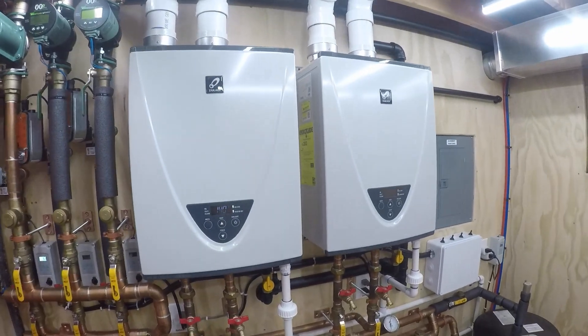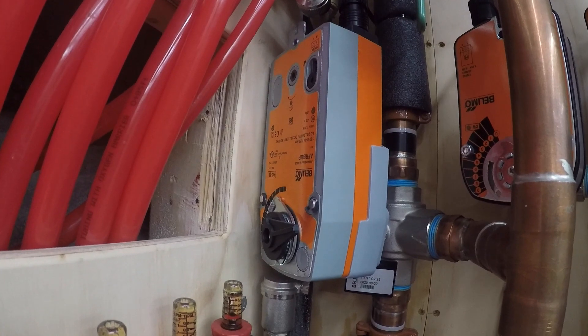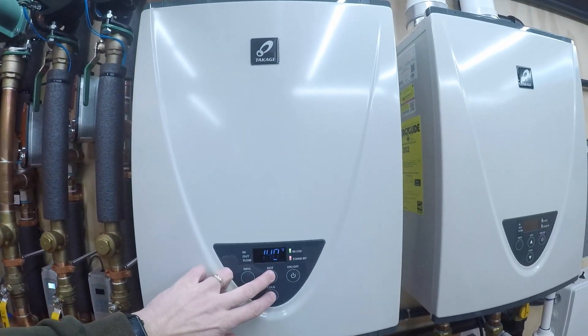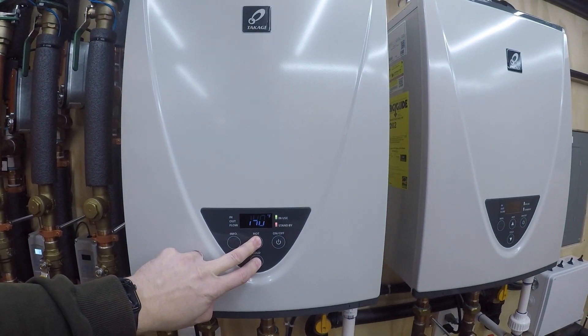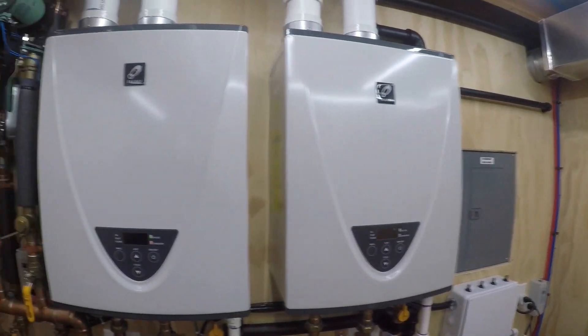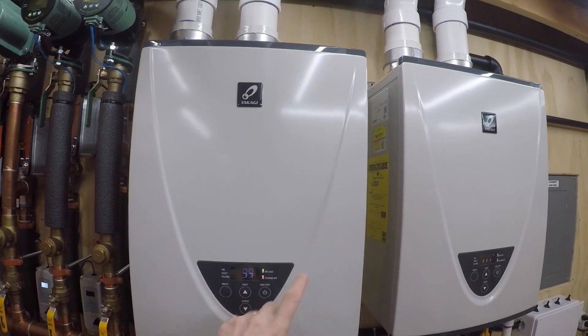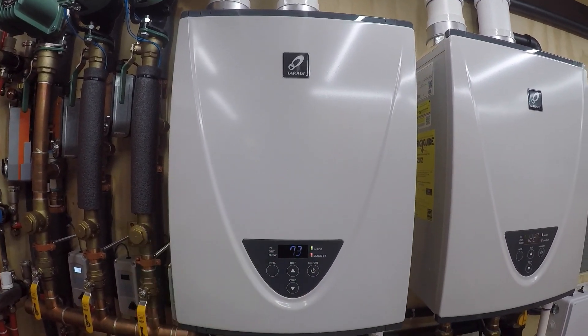Once that hits 65 — any second now — 65 kicks on the primary loop pump, heaters fire, and the Belimo valve slowly starts to open up.